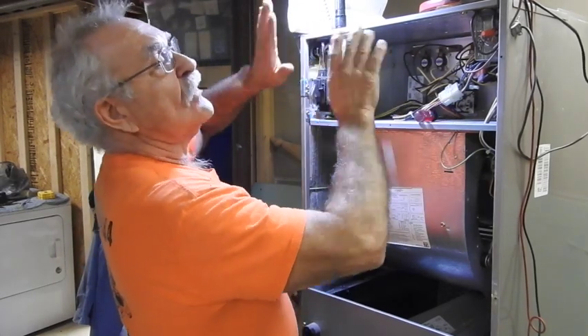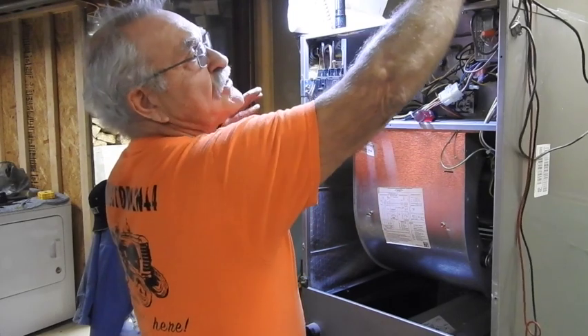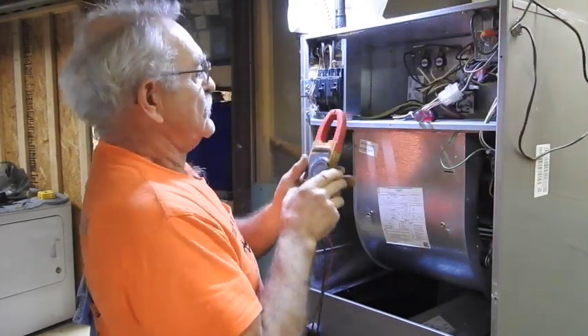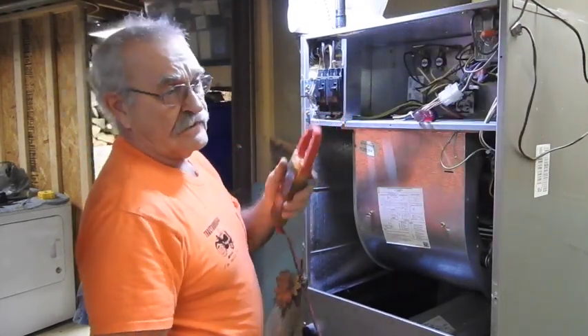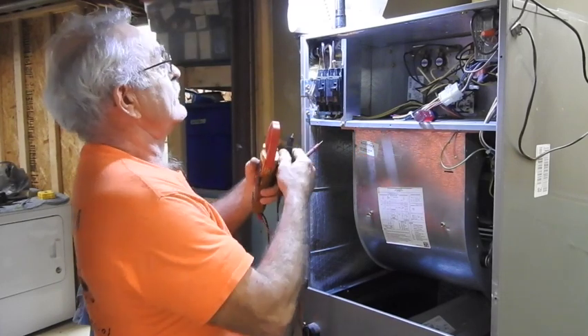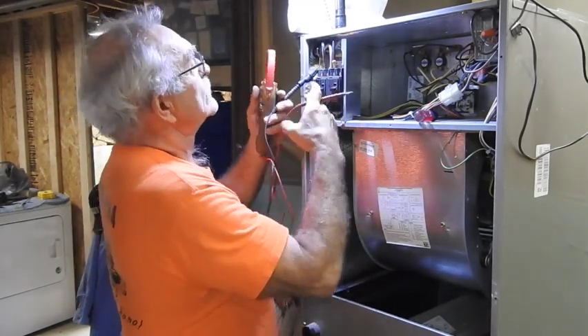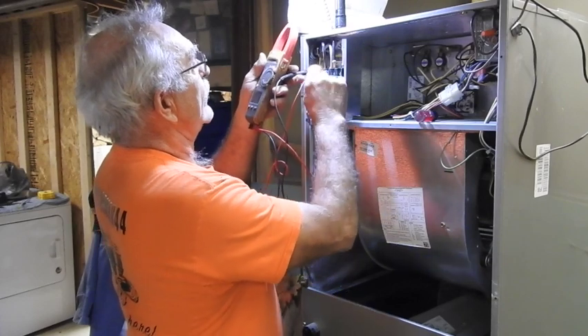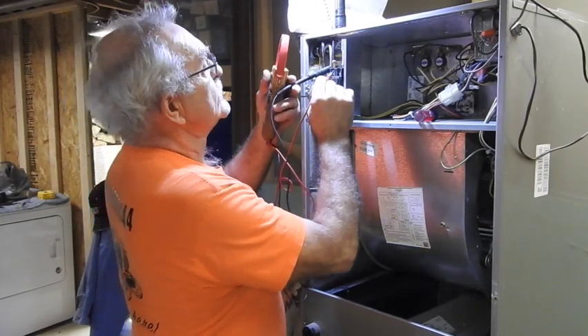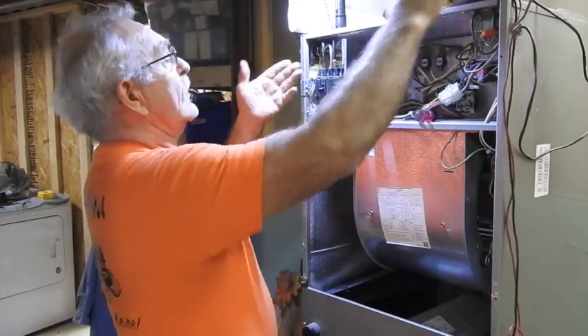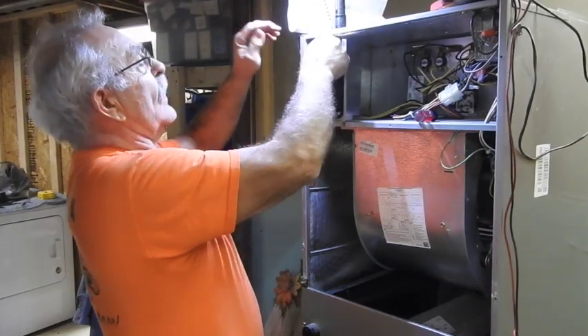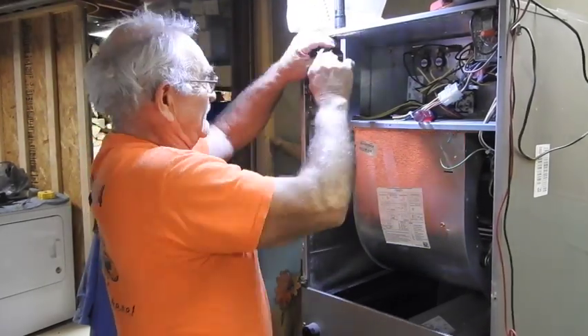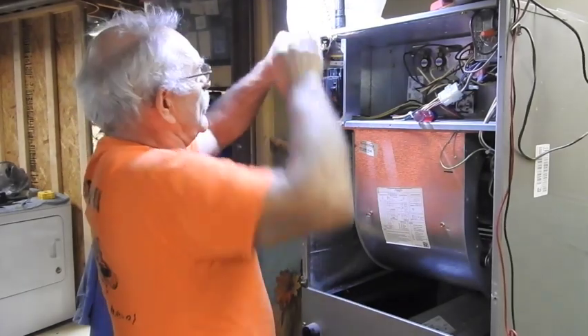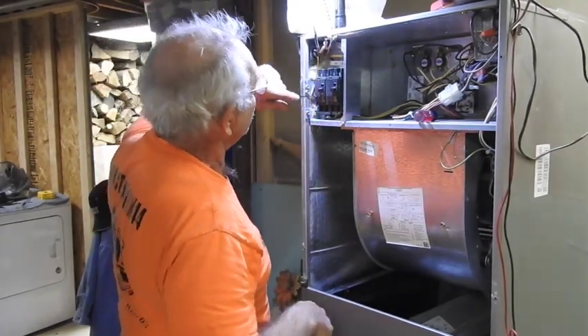And just for the heck of it, we've got everything disconnected. You can always double check again. It doesn't hurt a thing just to double check to make sure that you didn't read the meter incorrectly or something wasn't making contact. So you can just go right here on the wires before you take them out. Verify there's no voltage there at all. Now you can, with confidence, reach in here and pull these wires back. And then we've got the ground. We've got to get the ground off in here.